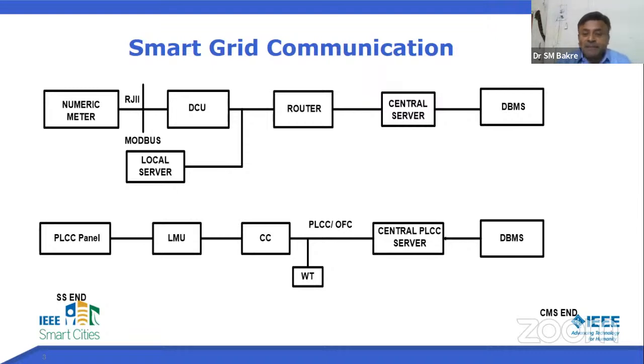The general setup of AMR is like this, starting with the numeric meter at the substation end, and the other end is the SLDC end or central server, CMS, whatever you call it. So there are two ends, substation end and CMS end. At the substation end the meters are installed, and at the CMS end the server is provided, which receives data all the time, 24/7, from substations.